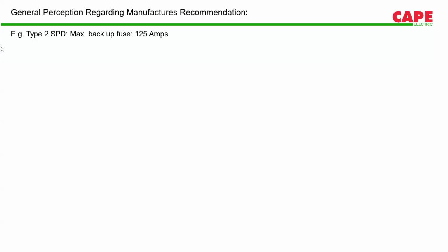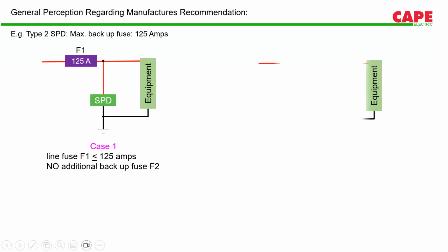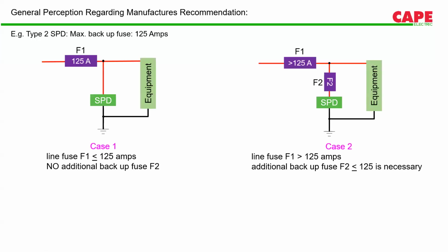Okay, you can start. Fine. So now there are two conditions. As I told, we need a backup fuse because in case the SPD fails in a short circuit mode, we need a device which can disconnect the SPD from the circuit. Now there are two cases. Normally, if we see a manufacturer's catalog, there will be a point written as maximum backup fuse up to X rating. Let's say in this case we have written 125 amps.